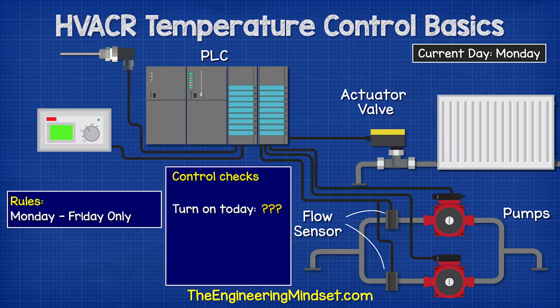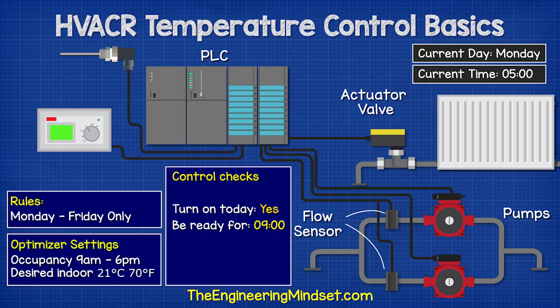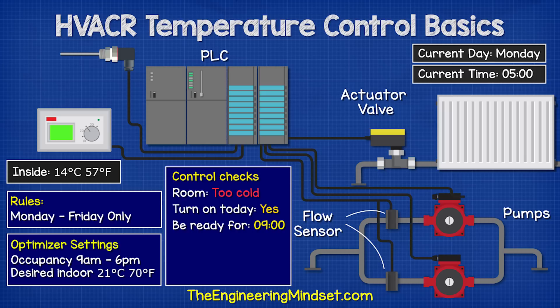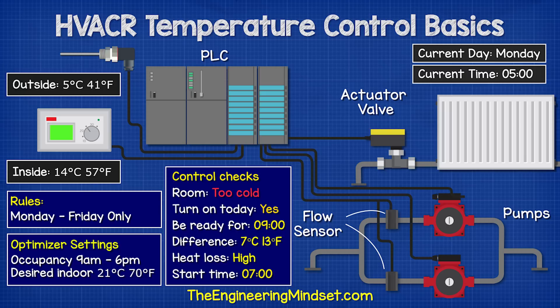This will check with the clock: should the heating turn on today? And if so, at what time will the building be occupied? The clock replies yes — the scheduled occupancy time is 9am. The PLC checks the current temperature of the room and calculates the difference between this temperature and the desired temperature. It then checks the outdoor temperature to calculate how long it will take to heat the building, because on a cold day it will take longer, so it will need to start earlier.